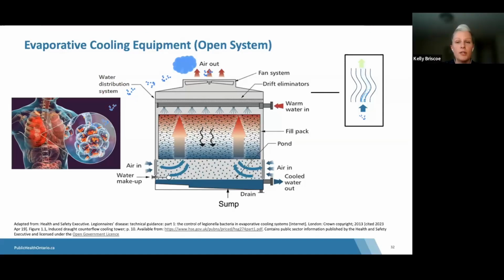Cooling towers can present a risk when they're poorly maintained or there's a lack of understanding of the system, if there's a lack of regular disinfection, improper restart and operating procedures, or if they're poorly designed in terms of layout or positioning—for example, if they're located close to air intake vents or open windows.